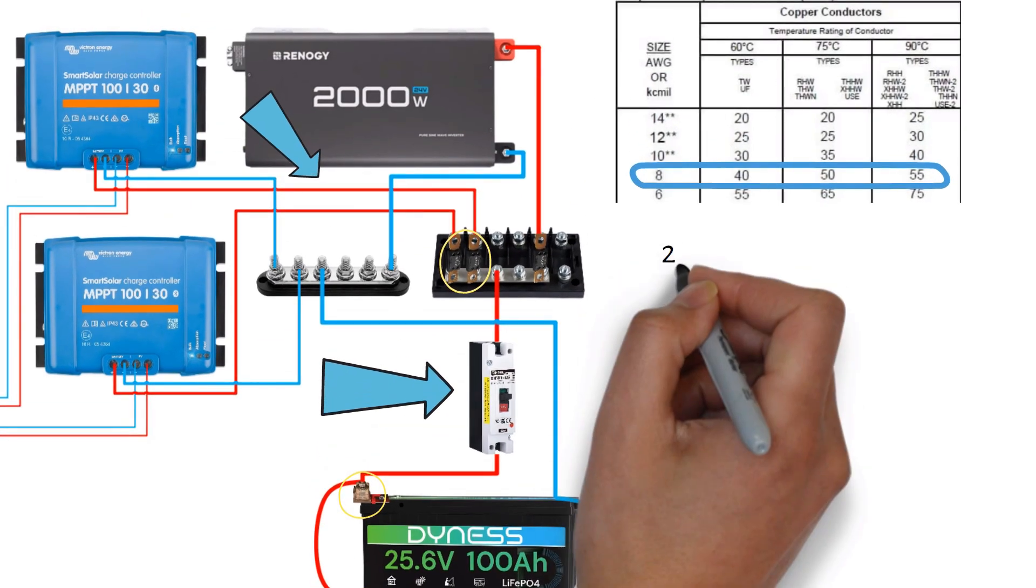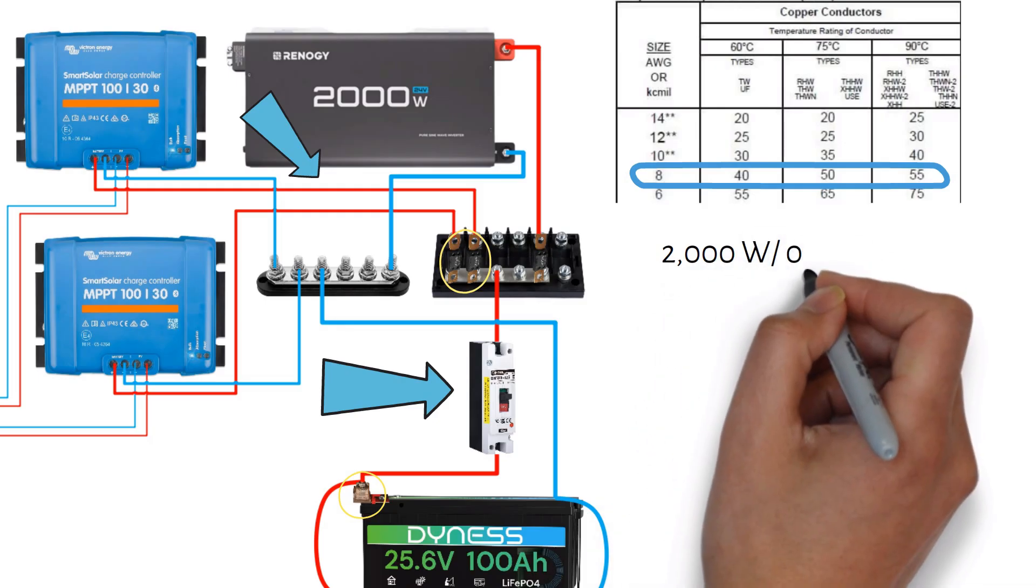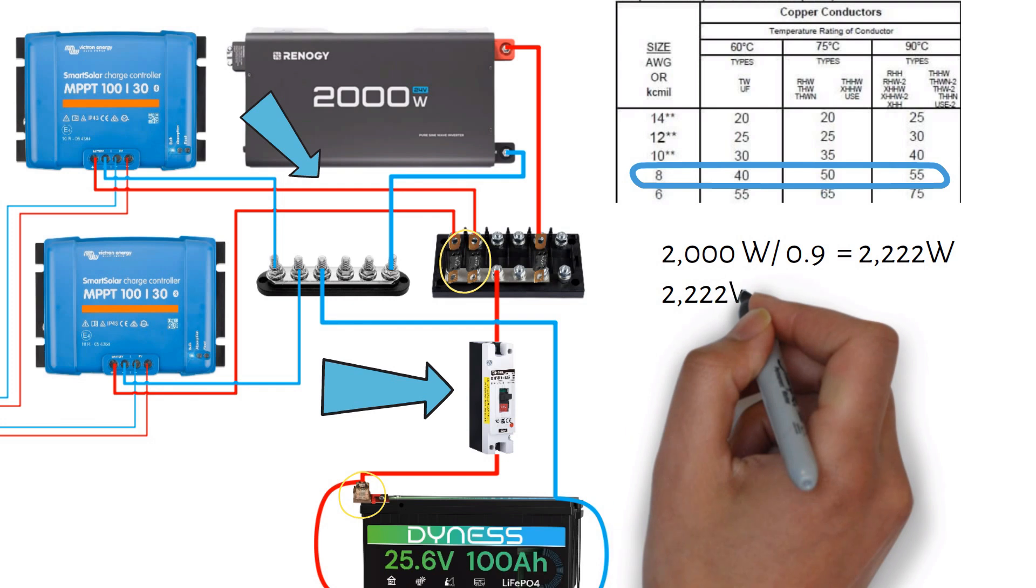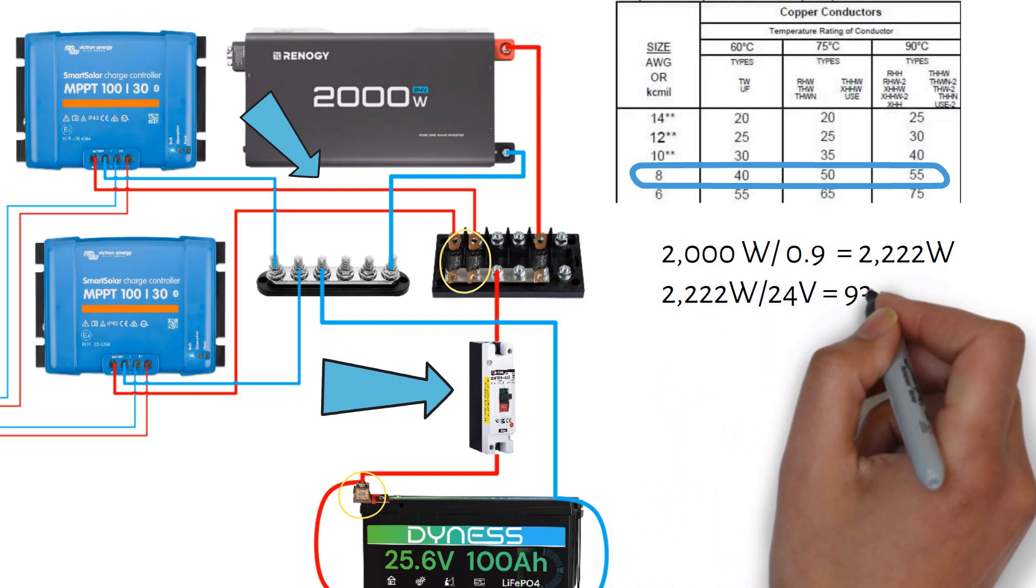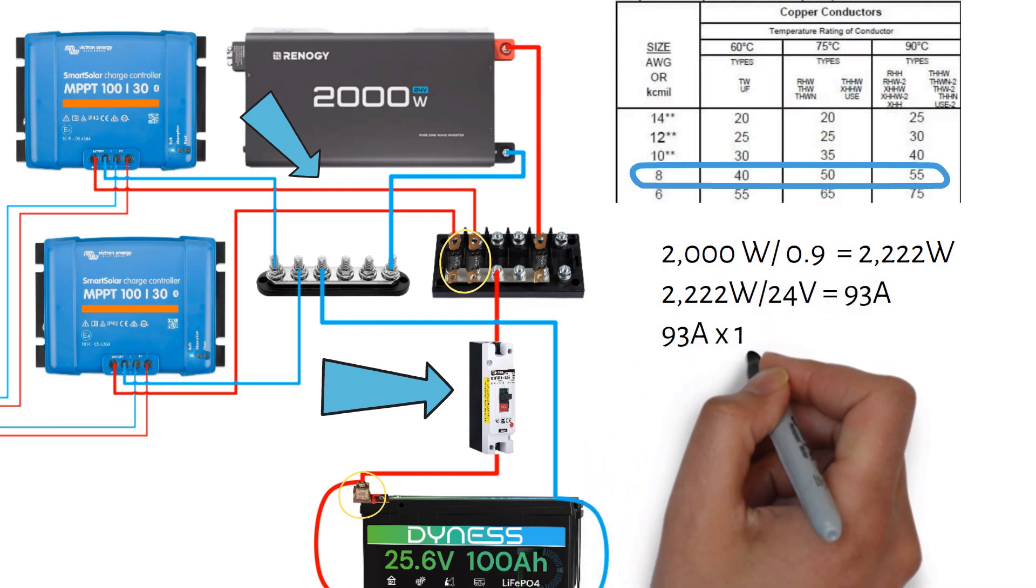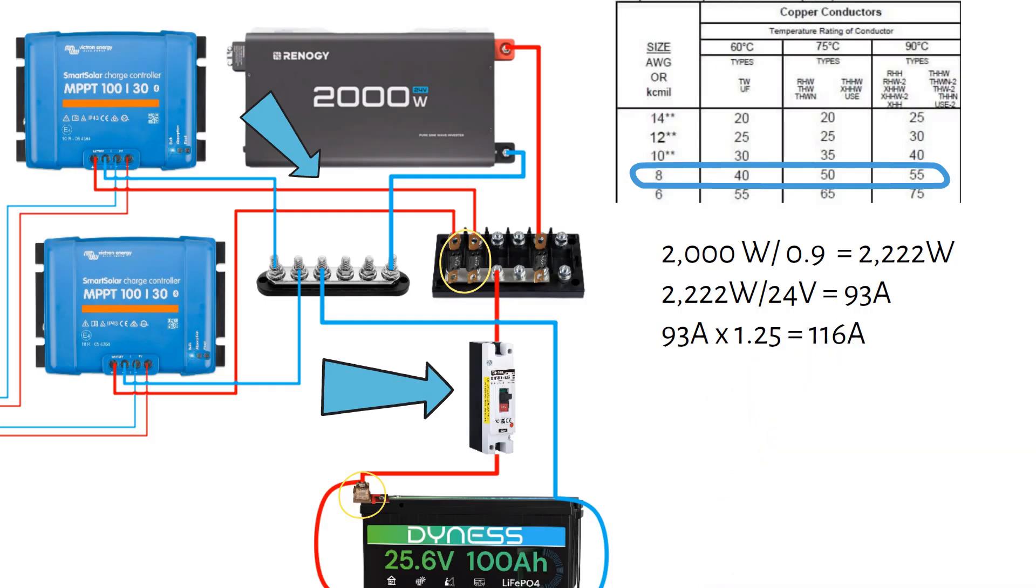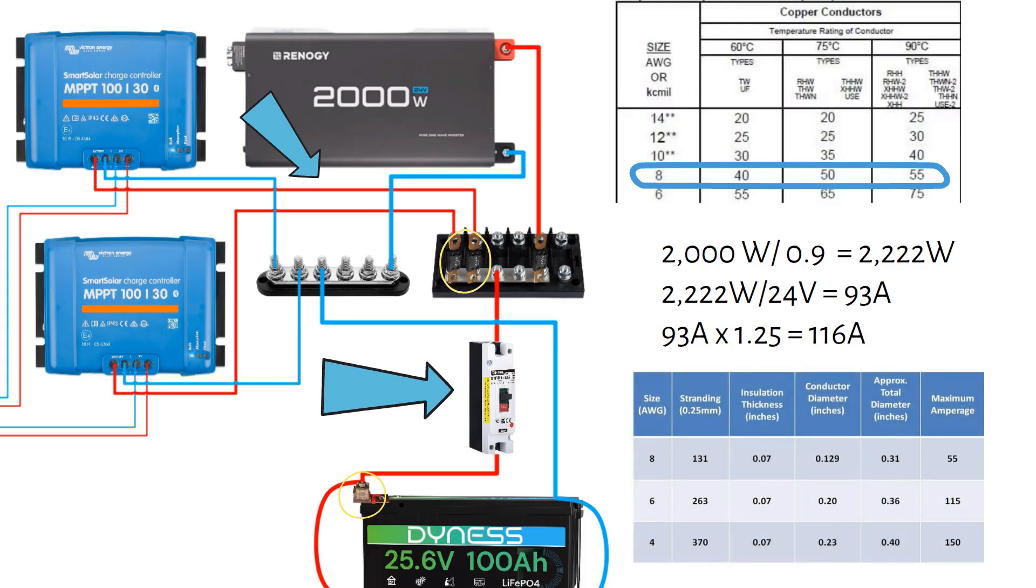The inverter draws a maximum of 2000 watts. Dividing by an efficiency factor of 0.9 and then dividing by 24 volts we get 93 amps. And applying a safety factor I get 116 amps. So I use a 125 amp breaker and a 4 gauge or 25mm square welding cable. The fuse and cable to the inverter is the same.